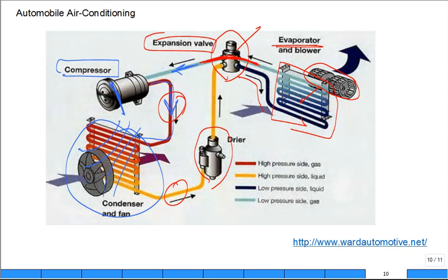And then it controls a little needle coming down here. And when it expands, because it's warm, it lifts the needle, lets more refrigerant go. And when it's too cold, it collapses, pushes the needle down, seats it, and shuts off the flow. So it's a control mechanism. So I'm going to pass that around for you.